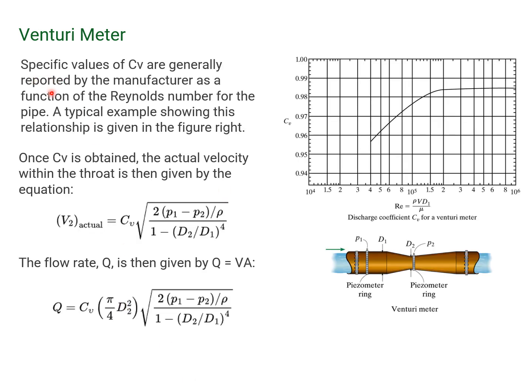Manufacturers typically produce a chart that gives you a way to calculate the actual velocity since the formula we showed on the previous slide is a theoretical value. Experimentally, the makers of the Venturi meter actually produce their own chart. They come up with a correction factor, CV, that's a function of the Reynolds number. Based on the Reynolds number, you come in, you get your CV value, and you multiply that by the theoretical velocity.